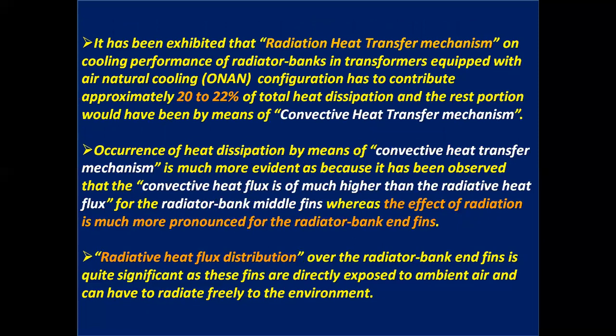It has been exhibited that the radiation heat transfer mechanism in the cooling performance of radiator banks in transformers equipped with air natural cooling, that is ONAN type cooling configuration, contributes approximately 20 to 22% of total heat dissipation, and the rest would be by means of the convective heat transfer mechanism. Heat dissipation by convective heat transfer is much more evident, as it has been observed that the convective heat flux is much higher than the radiative heat flux for the radiator bank middle fins, whereas the effect of radiation is much more pronounced for the radiator bank end fins.